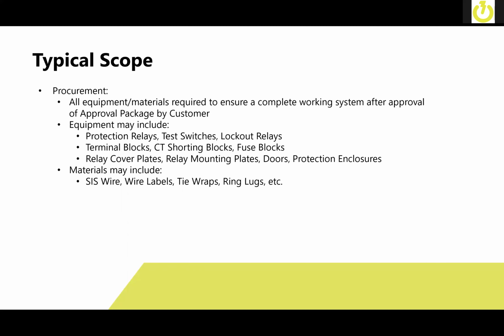Equipment can include protection relays, from a variety of manufacturers out there, test switches, lockout relays, and any terminal blocks for new wiring that needs to get installed, along with CT shorting blocks and fuse blocks, along with the fuses that go with those fuse blocks. Relay cover plates, relay mounting plates, doors, and protection enclosures in some cases where an entire new panel is desired. Materials a lot of times include SIS wire, wire labels, tie wraps, ring lugs, miscellaneous screws, nuts, bolts, etc. as required to get it installed.